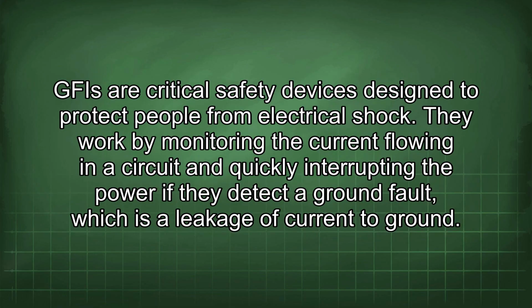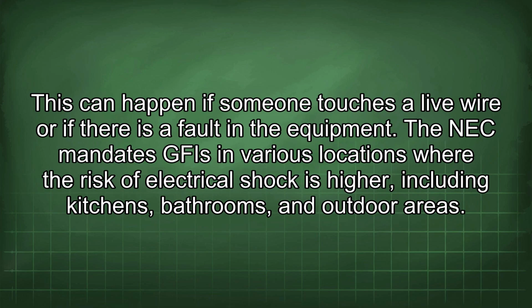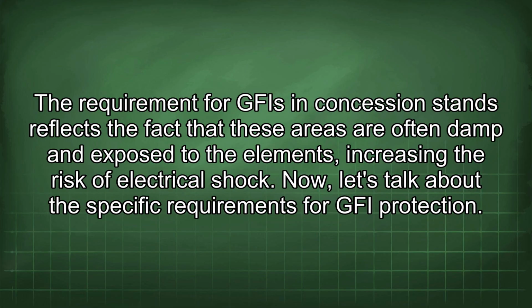GFI are critical safety devices designed to protect people from electrical shock. They work by monitoring the current flowing in a circuit and quickly interrupting the power if they detect a ground fault, which is a leakage of current to ground. This can happen if someone touches a live wire or if there is a fault in the equipment. The NEC mandates GFI in various locations where the risk of electrical shock is higher, including kitchens, bathrooms, and outdoor areas. The requirement for GFI in concession stands reflects the fact that these areas are often damp and exposed to the elements, increasing the risk of electrical shock.